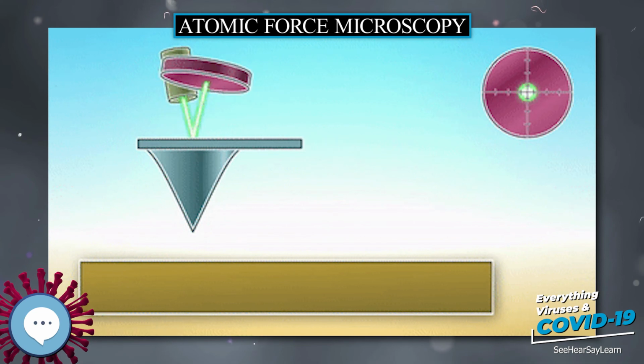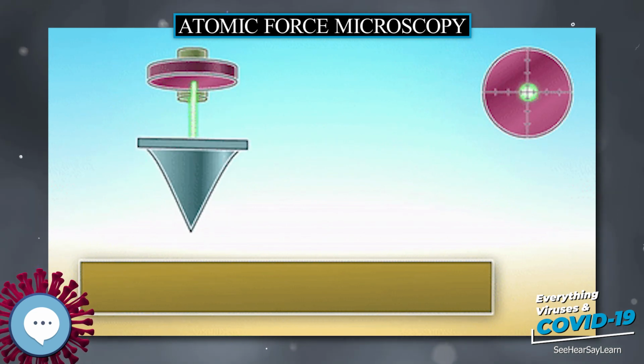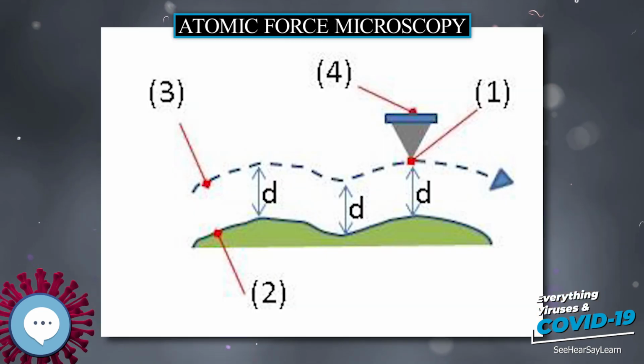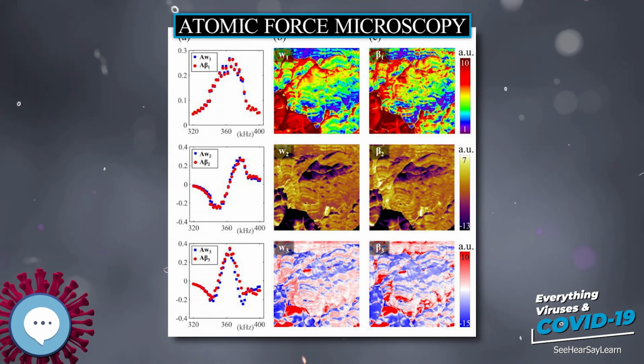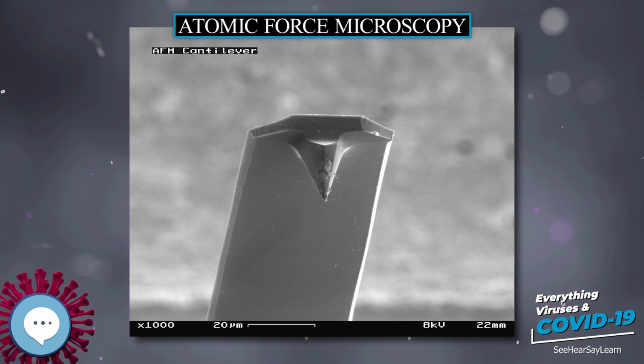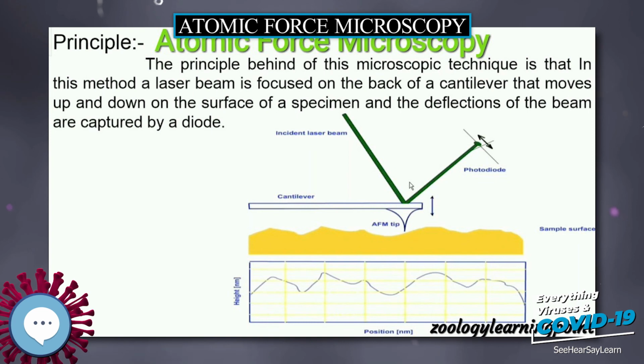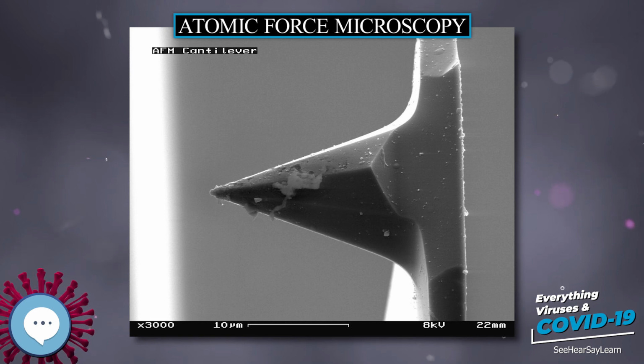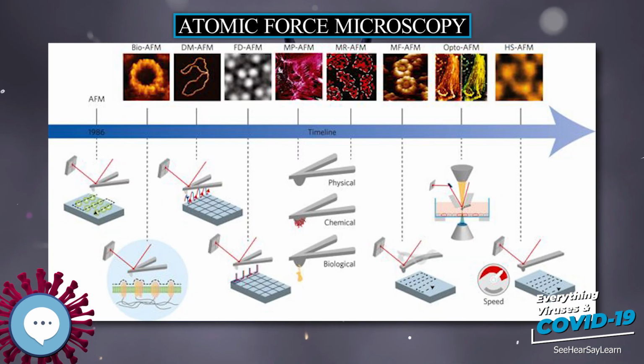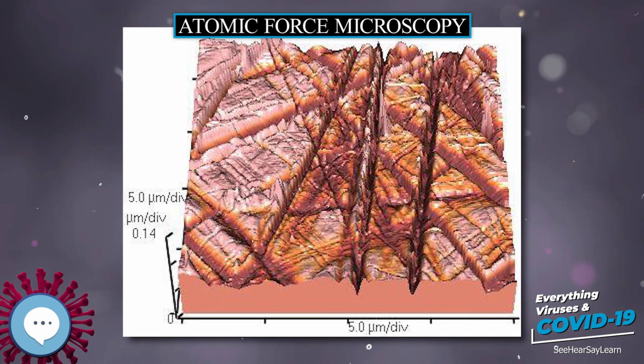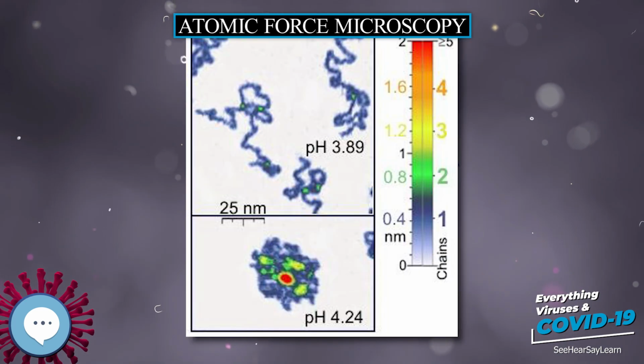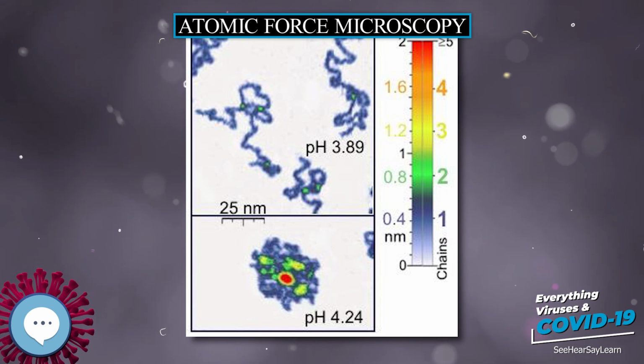Advantages and disadvantages. Advantages. AFM has several advantages over the scanning electron microscope, SEM. Unlike the electron microscope, which provides a two-dimensional projection or a two-dimensional image of a sample, the AFM provides a three-dimensional surface profile. In addition, samples viewed by AFM do not require any special treatments, such as metal/carbon coatings, that would irreversibly change or damage the sample, and it does not typically suffer from charging artifacts in the final image. While an electron microscope needs an expensive vacuum environment for proper operation, most AFM modes can work perfectly well in ambient air or even a liquid environment. This makes it possible to study biological macromolecules and even living organisms.